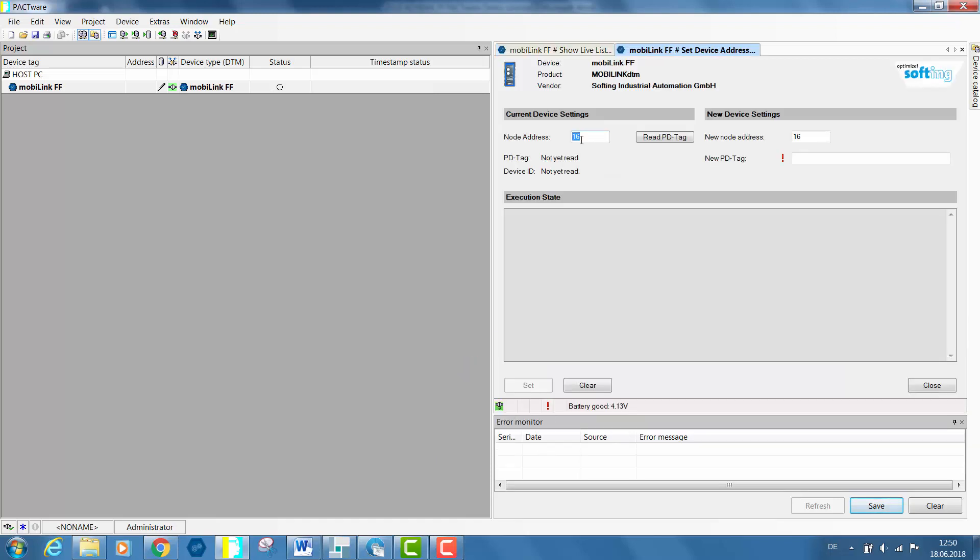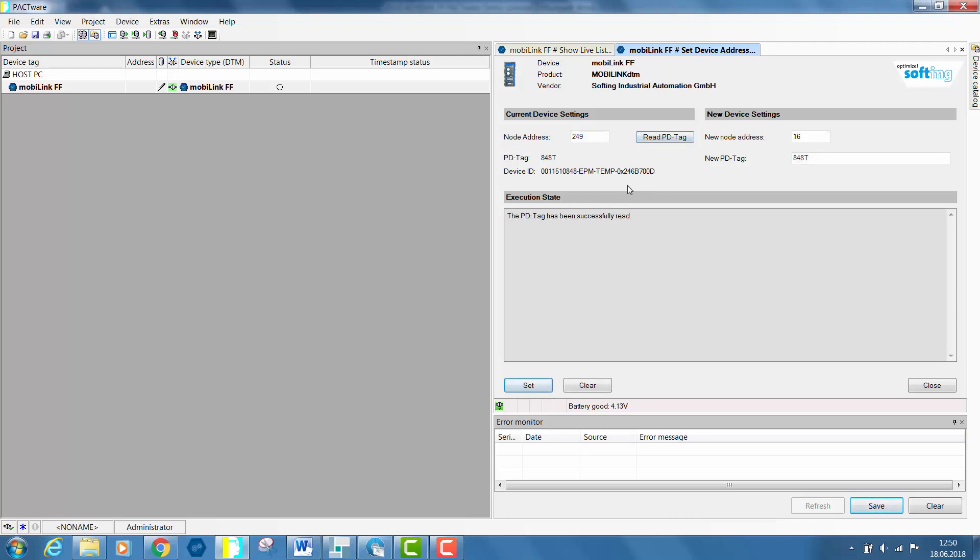Enter the previously identified node address 249 in node address and click on Read PD Tag. The Rosemount temperature sensor will be found. Enter in new node address, the desired address in our case 28, and set the value.